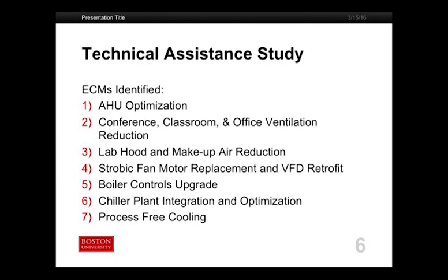And the air handlers were not optimized. We had some at 60 hertz, others, they wouldn't move from that. Others, the fan was completely stalled. So correcting our air handlers was job one. The next bit was that the conference rooms, the associated classrooms, office, they just blasted 24/7. So our control strategy was just, let her rip.